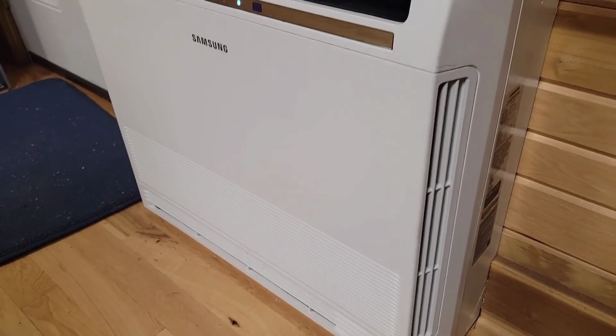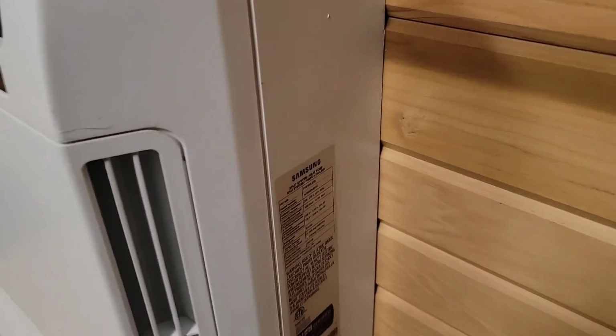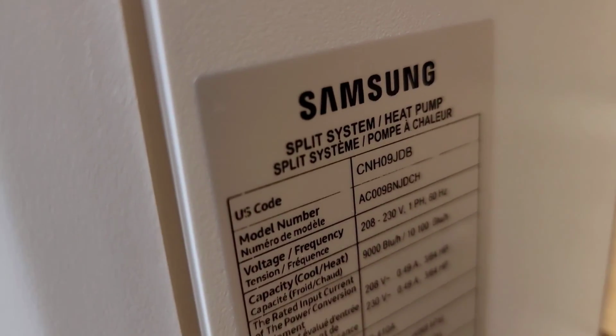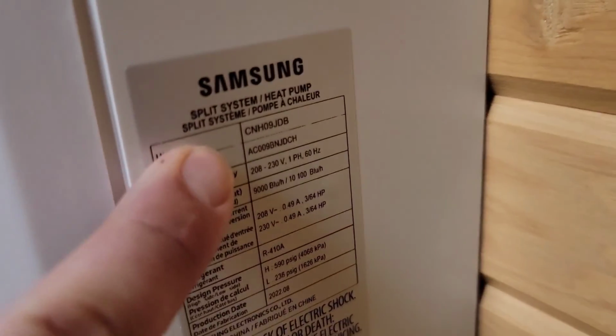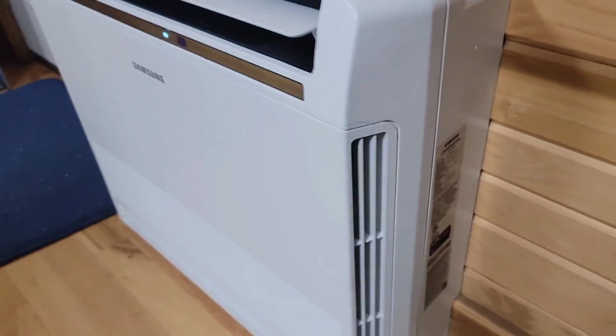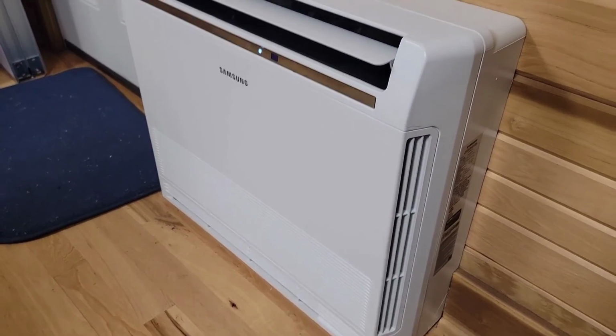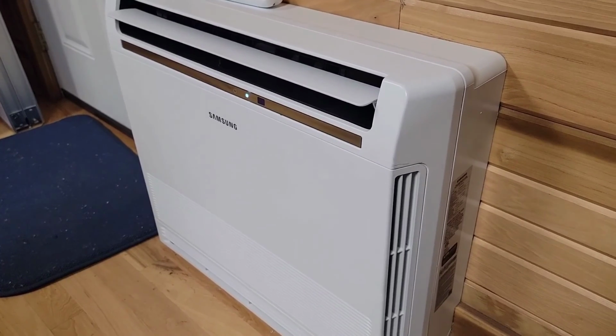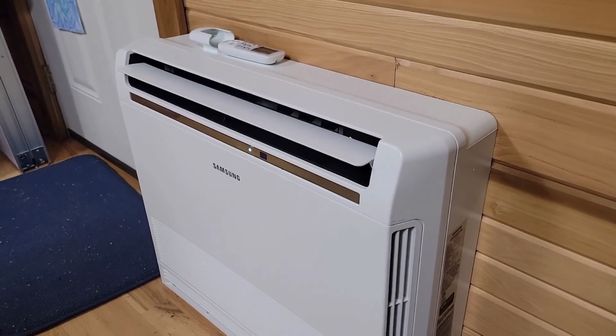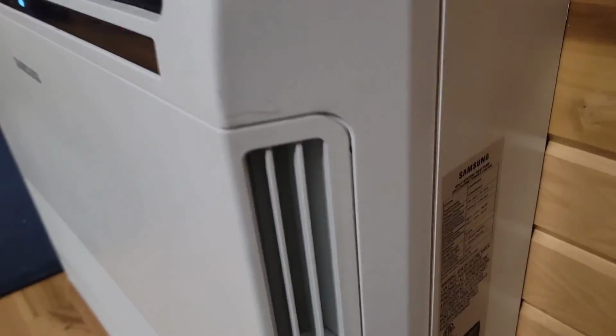All the units are set on 70. They're all heating. Make sure I have my model numbers. This one's the only one that's different. Make sure I got them all, that way I can option code. Go ahead and do the thermal off, fan off. And then also I'm going to remove that compensation, that 5-degree compensation.